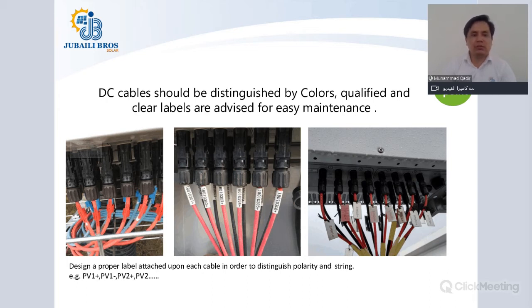DC cables should be distinguished by colors, and qualified and clear labels are advised for easy maintenance. Normally, what we have seen is that when people win their projects, they become too much in a hurry in procuring the things, and sometimes they buy both the polarity cables of the same color. Both could be red, both could be black, and such a cabling method will lead to wrong string connections to the inverter and wrong polarities. So you are highly advised to have two different colors, and normally red and black is preferred for connecting your solar PV strings to the inverter.